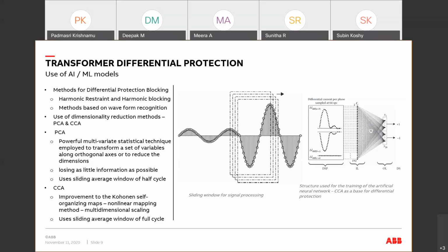These 192 elements are stored for every single vector and arranged as a training matrix. The training matrix will have a dimension of 192 into n, where n is the number of test cases that you could identify. The test cases can run in hundreds because we are talking about R phase short circuit, inrush current, various phenomena multiplied into the 3 phases. We can have a huge number of test cases planned. So from this, it identifies the decision signal, and that makes it capable of distinguishing between the inrush and the short circuit current. So that's how the CCA works.